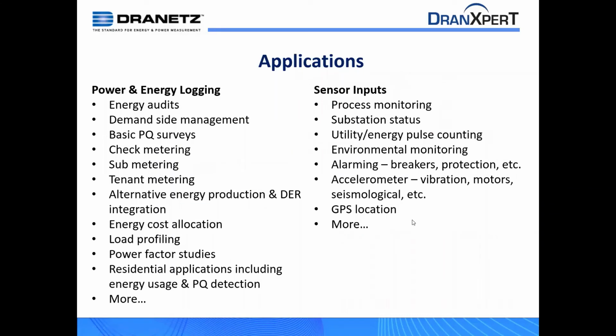So to wrap this section up, what are the applications of DranXperT? It's really any application that requires power measurement and or environmental measurement. So energy audits, demand side management, basic power quality, even check metering applications, which is a requirement in certain districts and certain towns and cities and states. Sub-metering, tenant metering, which is becoming more and more popular, alternative energy production, or what are you producing versus what are you consuming at a particular point in your facility or in the grid for a utility. And all these other applications out there, and popular ones are also power factor studies.